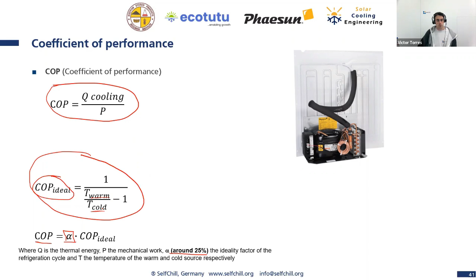I calculated for you, if we have a cold temperature of minus 3.5, which is the temperature we normally have in the water chiller when we are producing ice, and depending on the ambient temperature, we will have these COPs. Now I would like to concentrate here on 30 degrees and operate with a COP of 1.75.